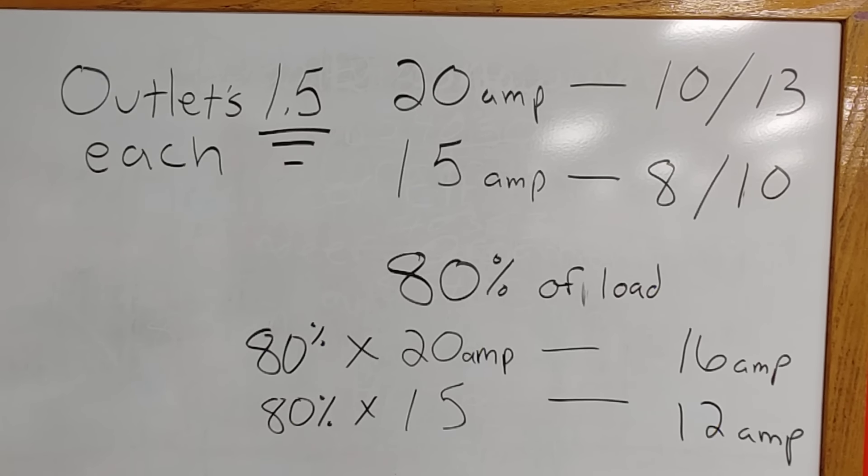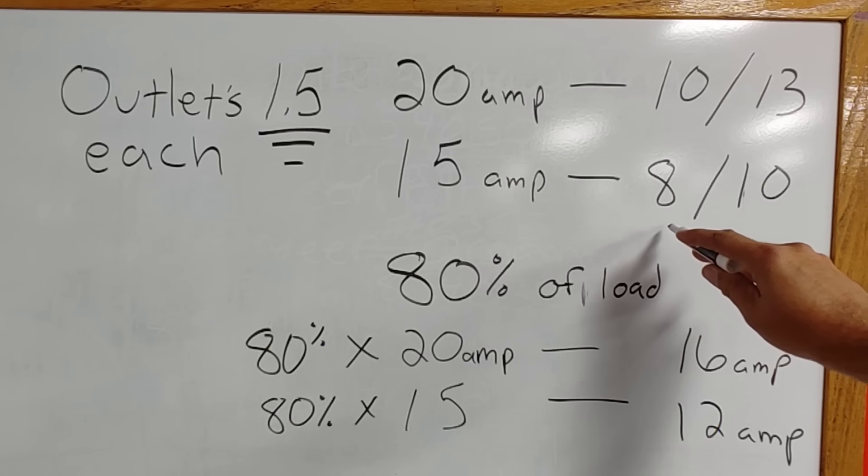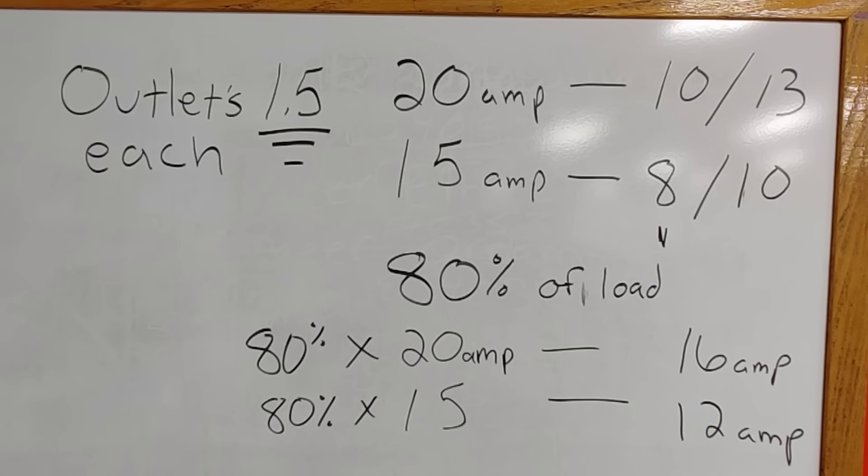The first school of logic is you should only put 8 outlets on a 15 amp circuit and 10 outlets on a 20 amp circuit. But some people also think you should put 13 on a 20 amp circuit and 10 on a 15 amp circuit.